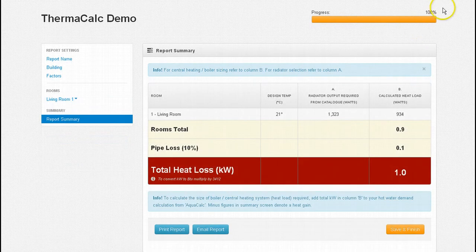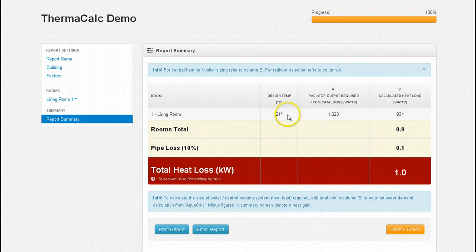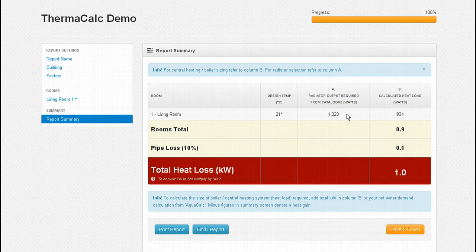Our report is now 100% complete. There are 3 main columns titled design temperature, radiator required from a catalogue and calculated heat load. The design temperature displays either the default or our manually adjusted room temperature. The radiator required from a catalogue in column A is the actual radiator output or heat emitter size needed for your room, which in our case is 1323 watts. This will be your selected radiator size, heat pump or underfloor heating selection for the room. The calculated heat load in column B is simply the output energy required from the heat source or boiler for the room — so for boiler sizing refer to this column.